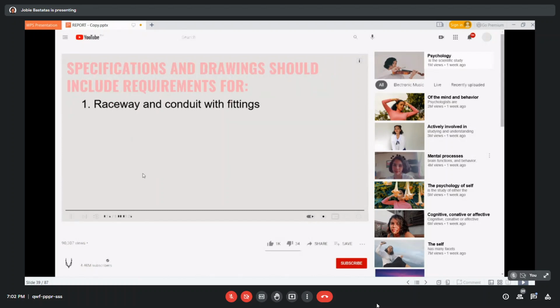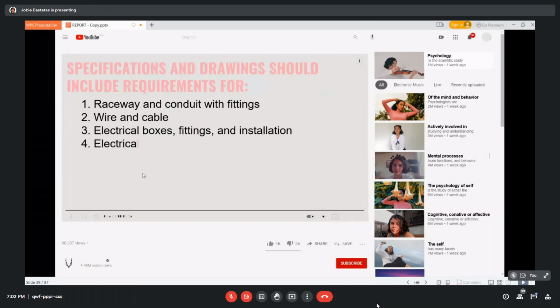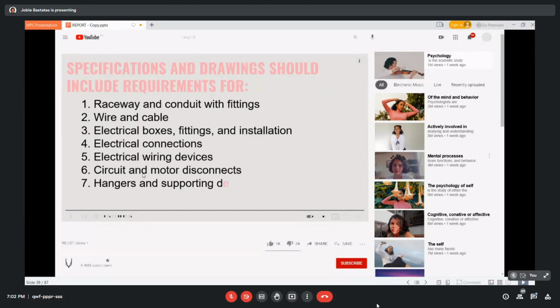Let's talk about the specifications and drawings that should be included in the requirements. First, raceway and conduit with fittings. Raceway and conduit with fittings are used to conceal exposed wires for giving the system an aesthetic appeal. Two, wire and cable. They are both electrical conductors, but the difference between the two is that wire is a single electrical conductor, whereas cable is a group of wires swathed with sheeting.